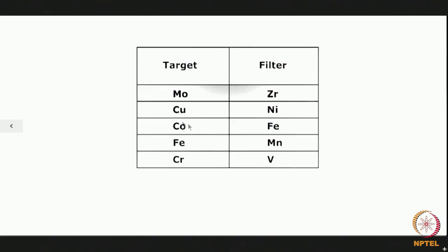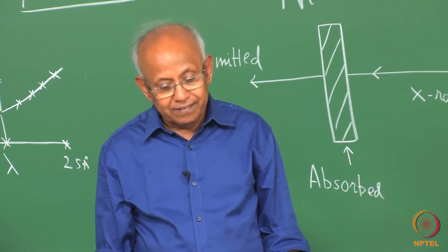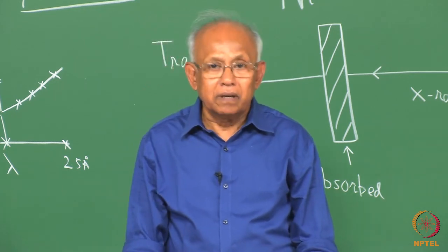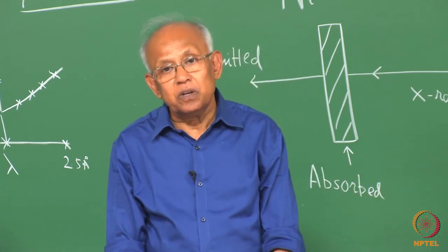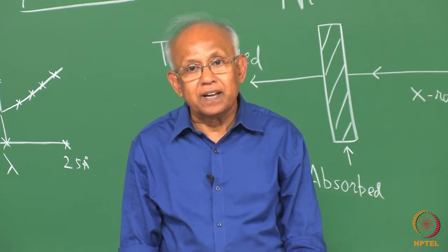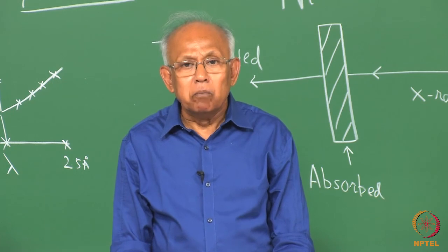For example, for copper it is nickel, you know atomic number difference is only one. In this way it is possible to figure out when you are using an X-ray machine with a particular type of target material, which material should be used as a filter material in order to get a more or less monochromatic or single wavelength radiation.